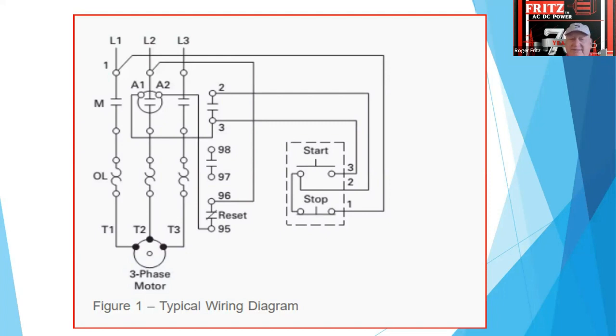Well, the motor is sitting here at standstill, so you get what they call inrush current. Normally the inrush current will be 5 to 6 times the running current, because once it gets going, it creates a counter EMF voltage inside the motor and resists the current flow. So that's why it starts up really high, then runs down.